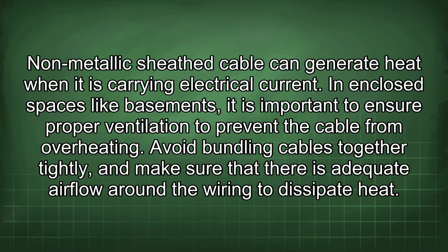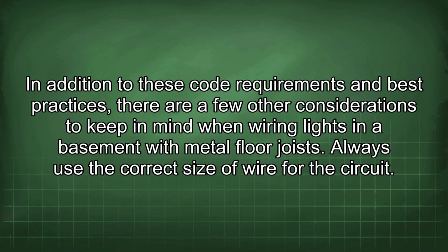Non-metallic sheath cable can generate heat when it is carrying electrical current. In enclosed spaces like basements, it is important to ensure proper ventilation to prevent the cable from overheating. Avoid bundling cables together tightly and make sure that there is adequate airflow around the wiring to dissipate heat. In addition to these code requirements and best practices, there are a few other considerations to keep in mind when wiring lights in a basement with metal floor joists.